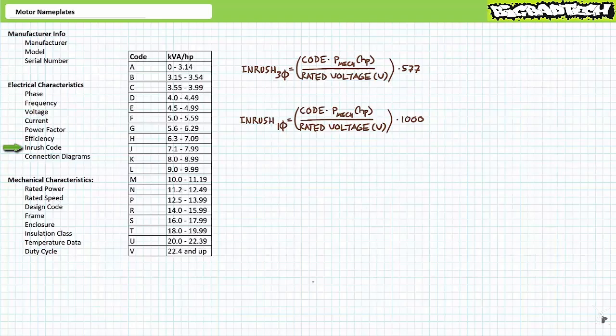As a rough estimate, most motors experience an inrush of roughly 6 times the rated current. Motors with a kilovolt ampere per horsepower code closer to A experience less, whereas motors with a kilovolt ampere per horsepower code closer to V experience more. We'll revisit inrush calculations and the electrical theory explaining inrush in later lectures, but let's try a simple example.